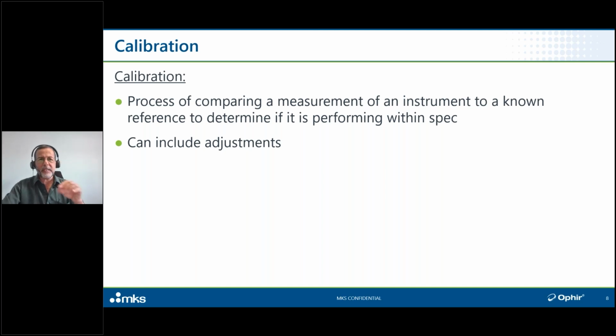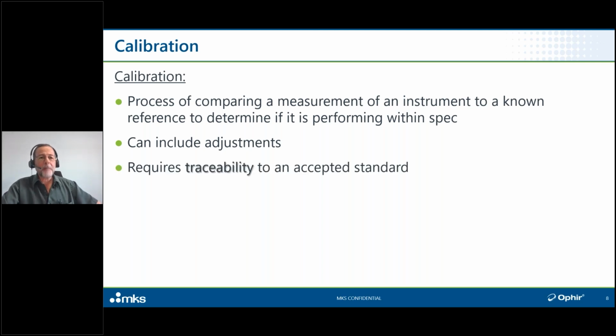Again, sorry for the hair splitting, but there are quite possibly some QA professionals among you, and I have to be accurate and precise in what I'm saying. Obviously, there has to be traceability to an accepted standard. Mostly in our industry, we refer to the American NIST as the standard, but it could just as easily be the German PTB or any other equivalent national standard body, as long as we both know what we're talking about. And there is a time limit, because at least in Ophir's case, the instruments that we make happen to be made of matter, and matter drifts over time and over use, but also over time. Even if there's no use, we're going to come back to that.